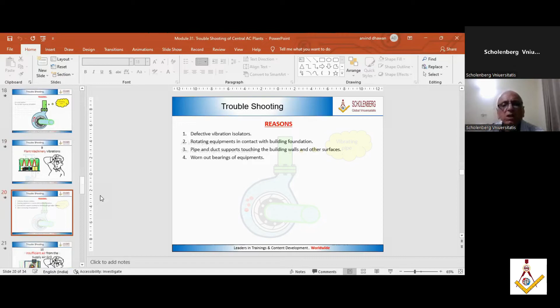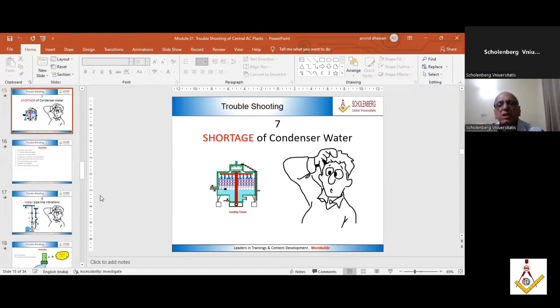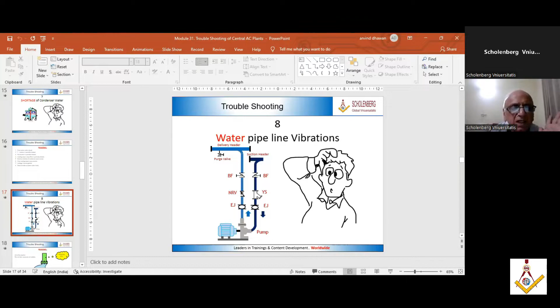Right? Another question just asked on this topic was, why does the water pipeline vibrate? Here we are. You must have noticed that sometimes these pipelines begin to vibrate violently. What's the reason? The reason is there's air in the system. This air causes knocking inside the pipeline, resulting in vibration. Not only that, it will damage the impeller also.